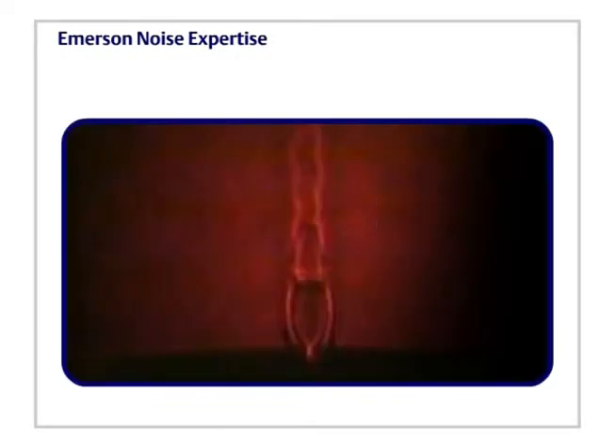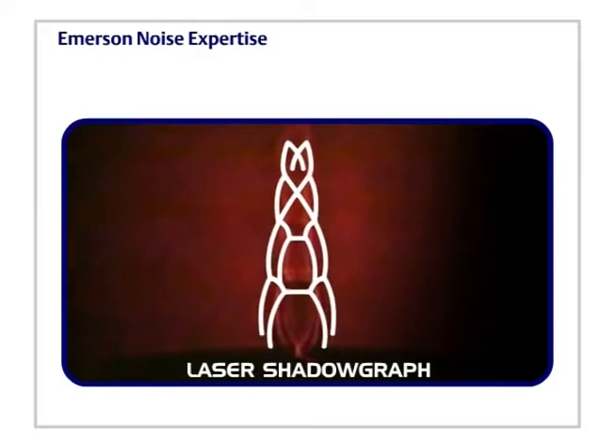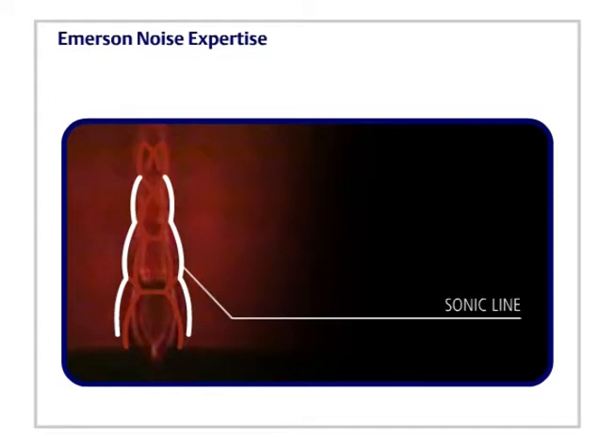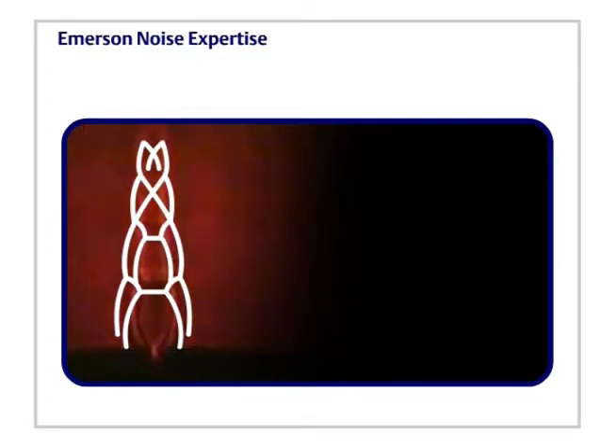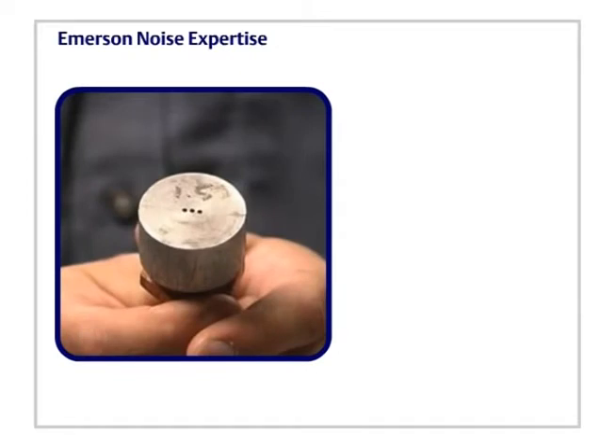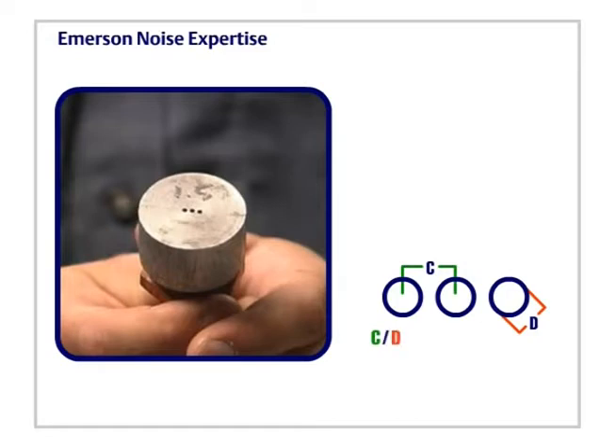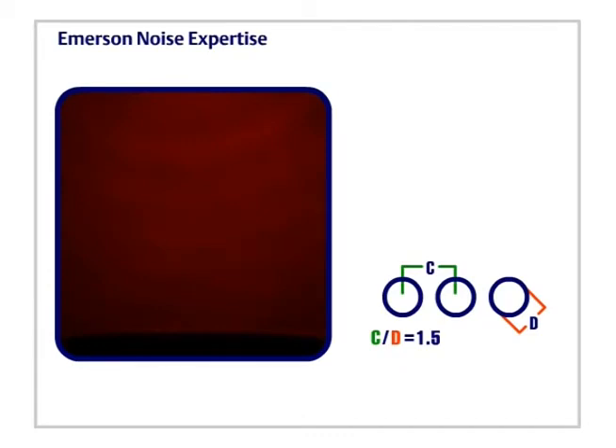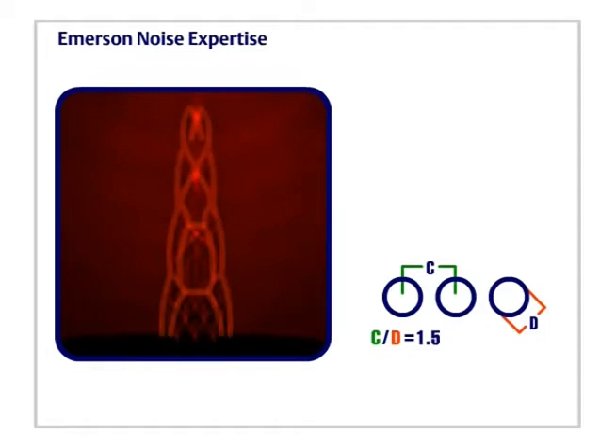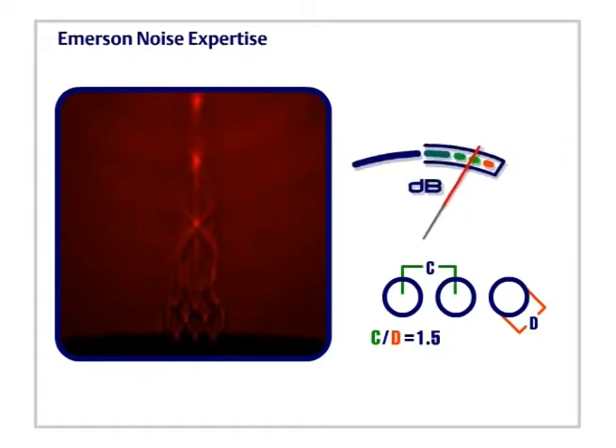Emerson uses laser shadowgraph technology to visualize and understand the differences between various types of noise reduction technologies for control valves. The following examples show the importance of jet separation to reduce noise radiation. This standard trim example demonstrates the use of a standard drilled hole: three holes, each one-eighth inch in diameter, spaced three-sixteenths inches apart, with a centerline distance to hole diameter ratio of 1.5. At low pressure, the three jets are independent from 0 to 50 PSIG. However, as the inlet pressure increases, the three jets gradually combine to become one large jet. This effect is detrimental to aerodynamic noise reduction. As the pressure drop increases, the combined jet structure continues to grow larger and noise level increases. Overall sound pressure level is 102 dBA.